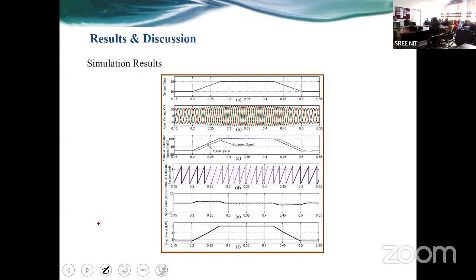See, if we are supplying the whole 100% power through the stator, then it is just like a SCIG. We are introducing variability, variable speed operation. If you are transferring 100% power, that means it is synchronized with the grid voltage, so no change in speed. Fixed speed operation will be there, so you cannot perform the MPPT. Variable speed turbines are coming into the picture only because they can extract the maximum power at different wind velocities. That 30% variation gives you sufficient capability, because the wind is also not varying from 0 to 100.